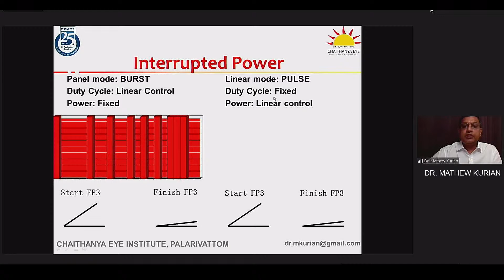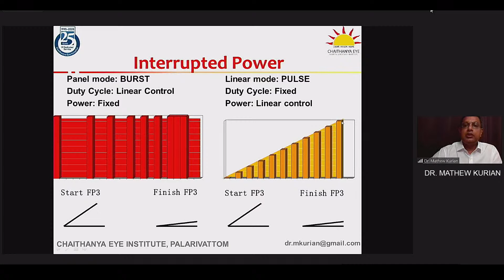In the other form of linear mode, which is called a pulse, you have a fixed duty cycle, which, let us say if it is 50%, you have half time on-off, and then you deliver the linear foot pedal control for power, which means as you go further down in foot position 3, you're delivering increasingly more power, though the gap between 2 on-off cycles never changes.